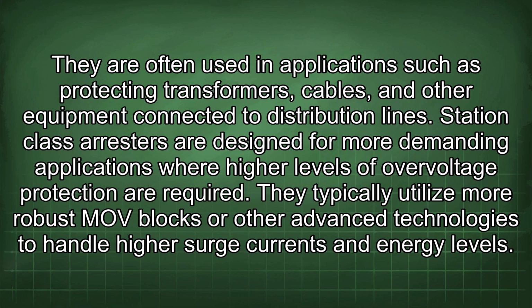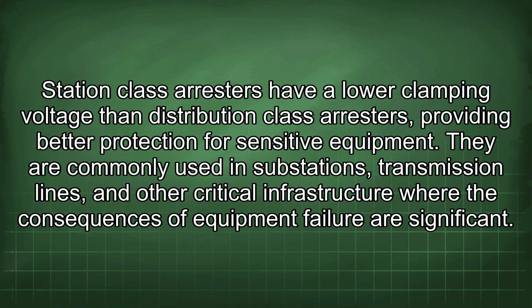Station class arresters are designed for more demanding applications where higher levels of overvoltage protection are required. They typically utilize more robust MOV blocks or other advanced technologies to handle higher surge currents and energy levels. Station class arresters have a lower clamping voltage than distribution class arresters, providing better protection for sensitive equipment. They are commonly used in substations, transmission lines, and other critical infrastructure where the consequences of equipment failure are significant.